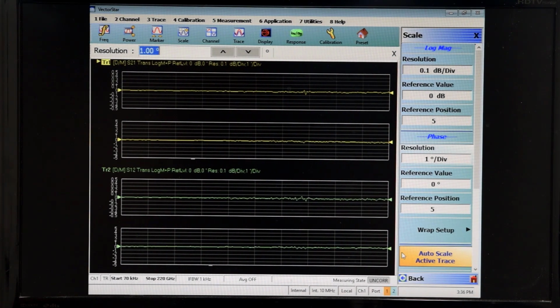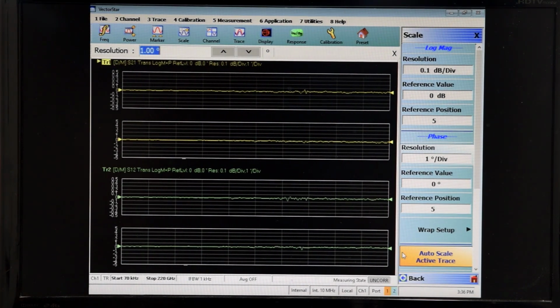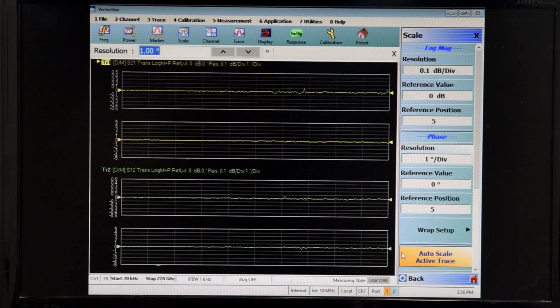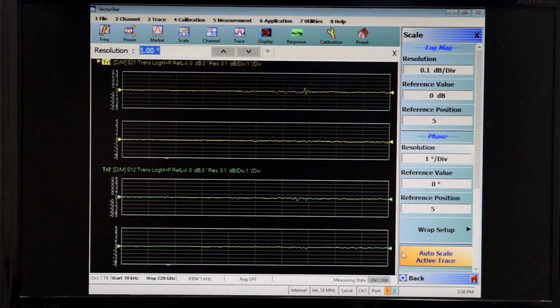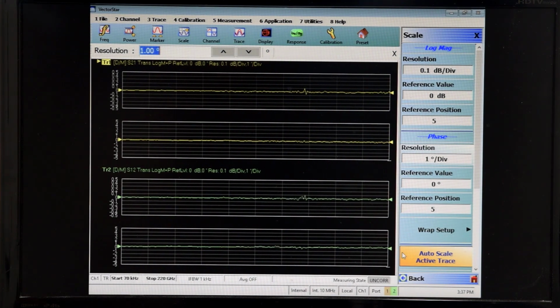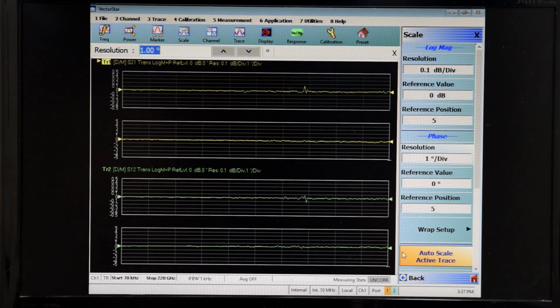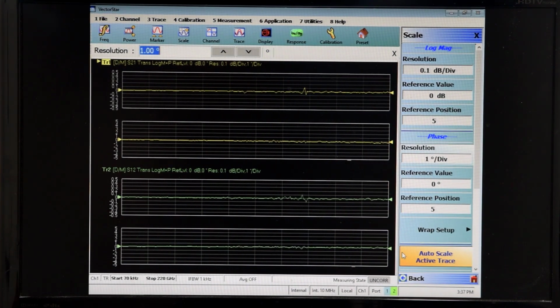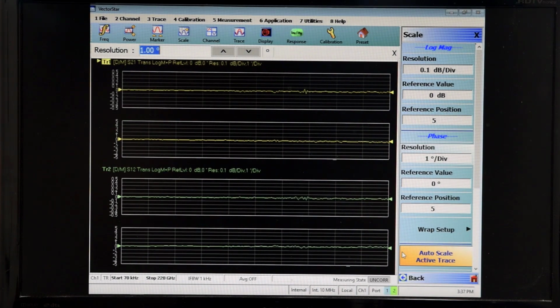Also, you want to keep in mind that if there is a wide variation in the temperature in your lab overnight, for instance, and you're running your stability tests overnight, you want to keep that in mind because the temperature variation is what's going to affect the overall system stability. And so sometimes it might be a better approach to evaluate that during the time when the temperature of the lab is more stable.